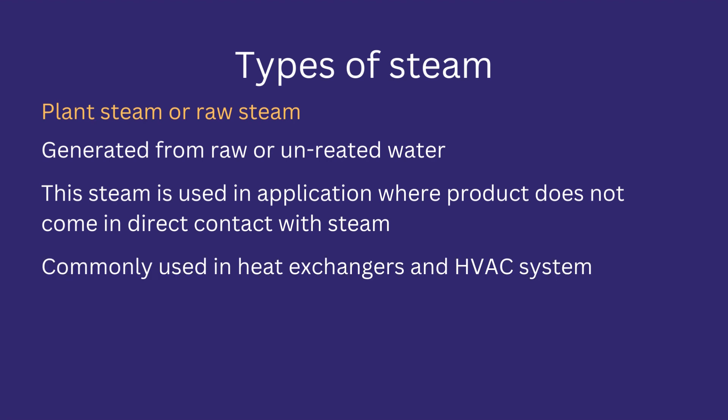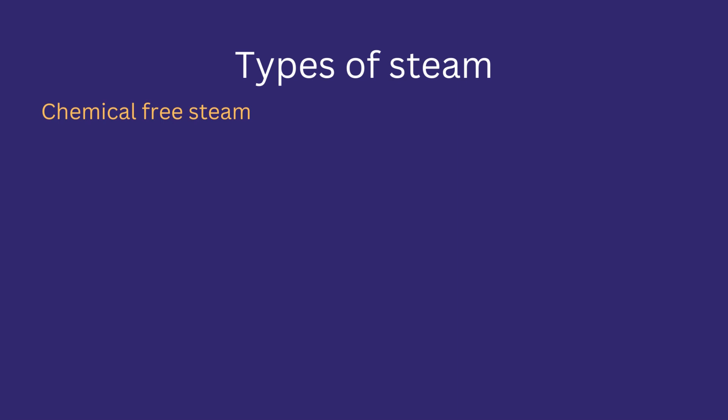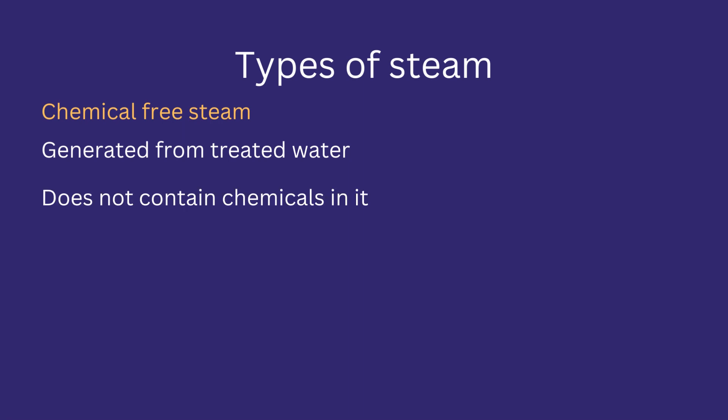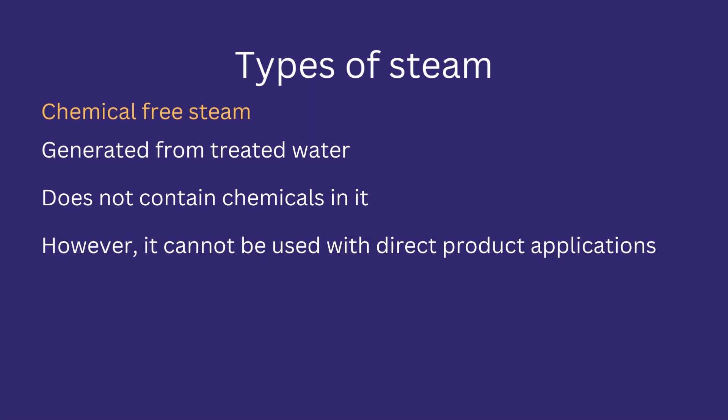Since plant steam cannot be used for critical applications, it can only be used for heat exchangers and HVAC systems. Chemical-free steam is generated from feed water that is free from chemicals and is treated before being fed to the boiler. However, chemical-free steam is not a pharma-grade standard and cannot be used for critical applications.